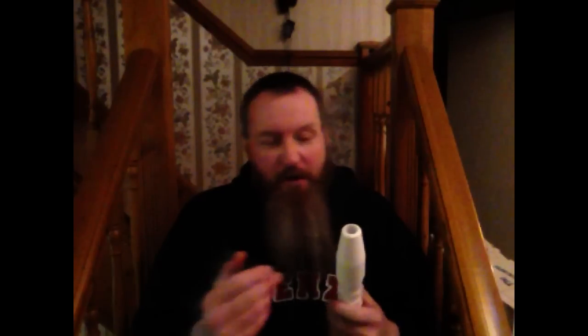And there is at least one documented fatality on the internet of someone actually holding one of these metal rods stuffed into one of these units because the way these circuits operate, it's what's called an Oudin coil. O-U-D-I-N coil. And it's got hints of Tesla to it. But unfortunately, the design of the circuit is such that it's pretty much referenced to the mains. There are versions that came out that they added the earth wire in and the secondary coil in this air core transformer at the end. It was referenced directly to earth instead of just coupling on to the primary, which is controlled for the mains.